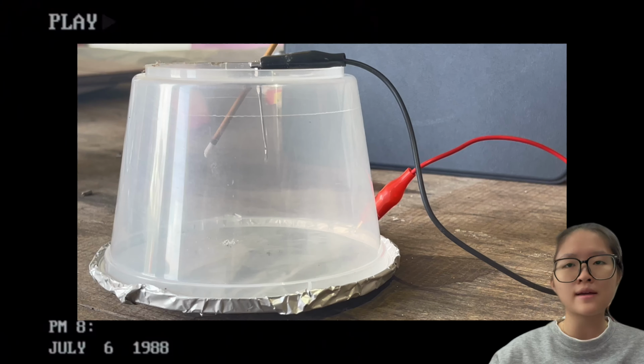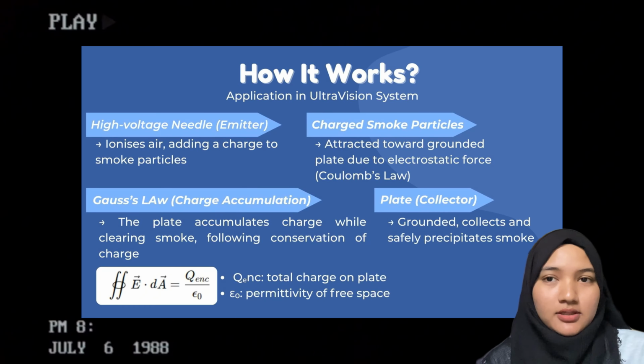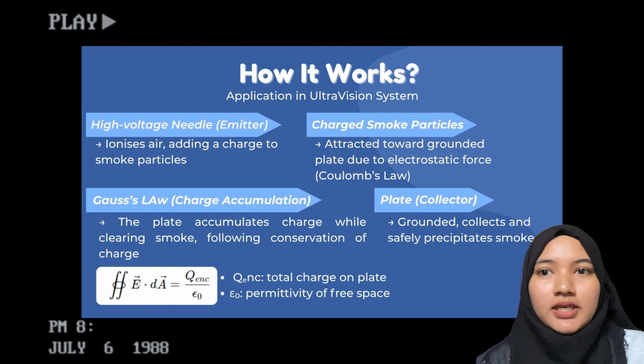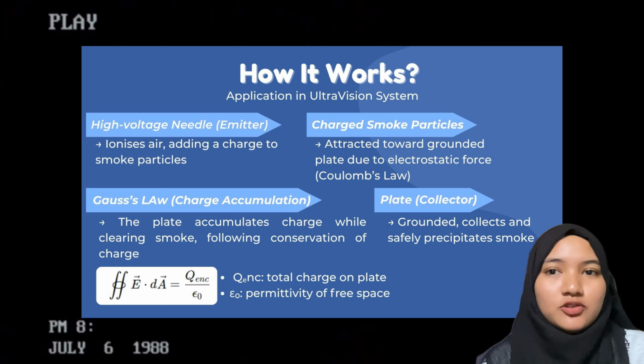The first one is the high voltage needle. The needle is connected to the ion generator, and the sharp tip of the needle will ionize the smoke particles with negative charges, according to the electric field theory. As a result, the smoke particles become negatively charged. Now, the smoke particles will experience an electrostatic force towards the less negatively charged surface on the plate, and the plate will safely collect them and ground them. The particles settle on the plate and accumulate, with conservation of charge as described by Gauss's law.